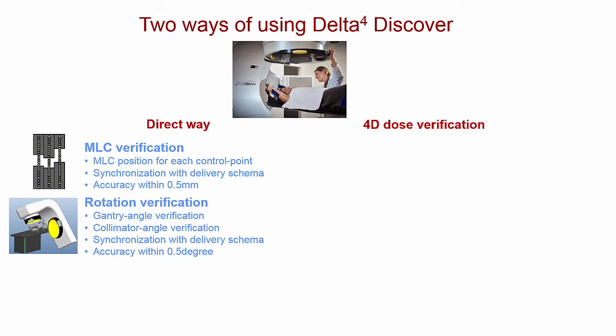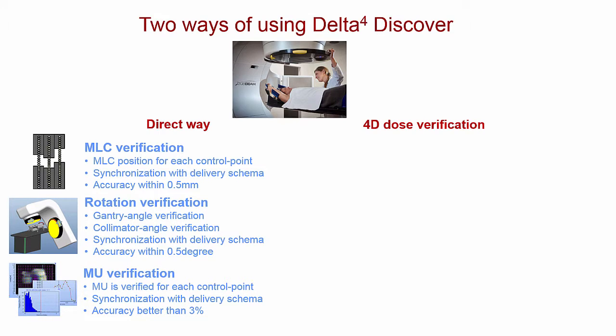We're also verifying the rotation completely independently, not just reading the log file from the treatment machine, but actually verifying both the gantry angle and the collimator angle rotation. And this is also synchronized with the delivery scheme. The accuracy is very good, better than 0.5 degree. Finally, on the direct way, we have the monitor unit verification. Per control point, we're verifying the monitor unit delivery. Also that is synchronized with the delivery scheme, and it has very good accuracy.